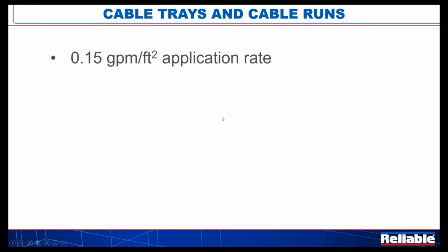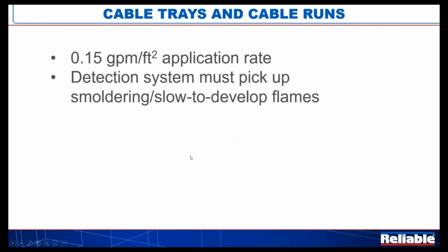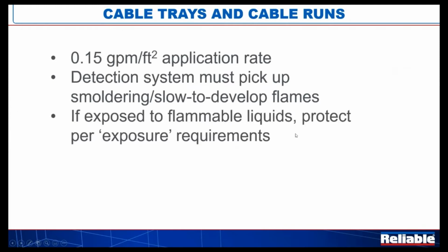0.15 GPM over every square foot application rate. So similar to sprinklers, we're looking at square footage and densities. And in that regard, the hydraulics, there's a section on hydraulics in NFPA 15 that I'm sure looks very much like NFPA 13. One of the things we want to do with these cable trays is pick up slow growing fires, right? We've got some wires that are shorting out or something's happening and things are increasing very slowly in speed. We want to pick that up very early on with this cable tray protection.